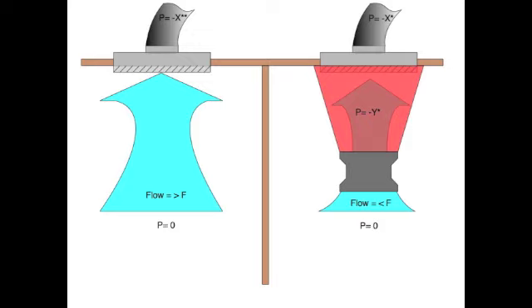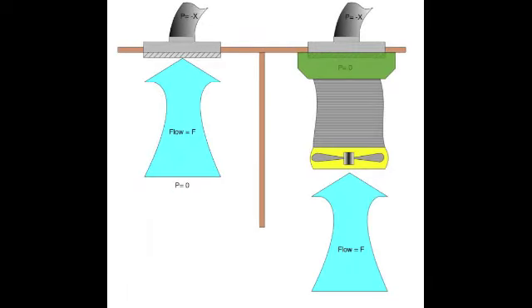This includes passive flow hoods and flow grids. One of the advantages of a powered flow hood is that it recreates the normal operating pressure at the face of the return grill, which is zero, which means that the flow is unaffected by the measurement tool. Multiple returns can be measured separately, and then the numbers can simply be added together to get an accurate total.